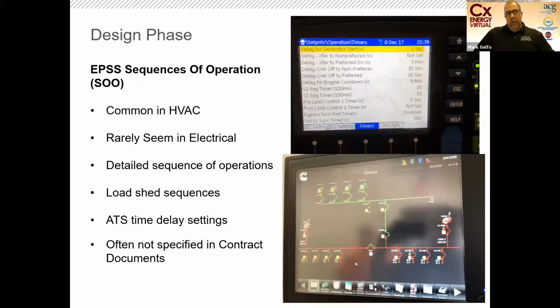Our mechanical brethren are very used to seeing detailed sequences of operations for how their systems work. But we rarely see a well thought out or well documented electrical emergency power system sequence of operations in the construction documents that lists how the system is supposed to operate, what's supposed to happen when we lose power, what the generators are supposed to do, details on the transfer switches and time delay settings and load shed sequences, and what happens when power is restored and goes back the other way.